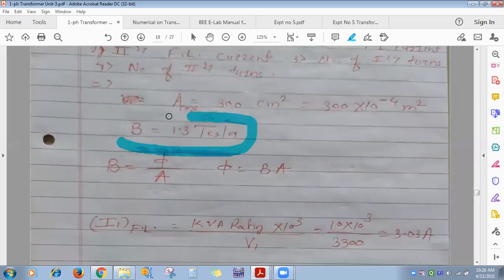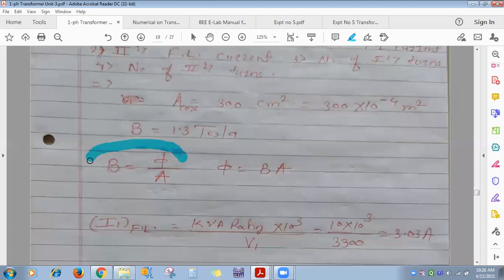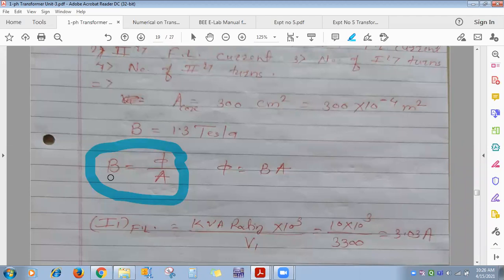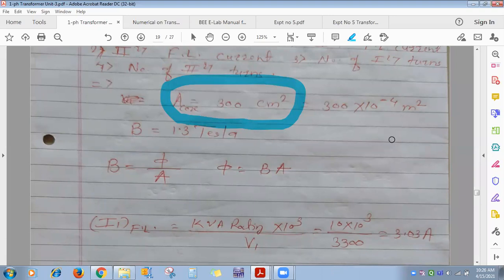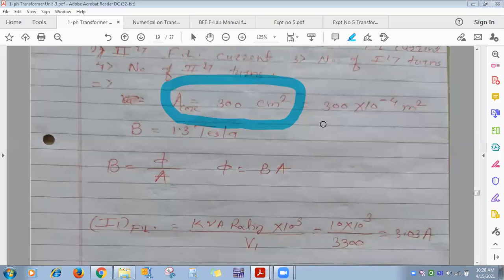Cross-sectional area = 300 × 10⁻⁴ m². Flux Φ = B × A. Replacing Φ in the EMF equation: E1 = 4.44·f·Bm·A·N1. Putting in all values gives N1 = 382 turns. In MCQ options, either 381 or 382 will appear — both are acceptable.